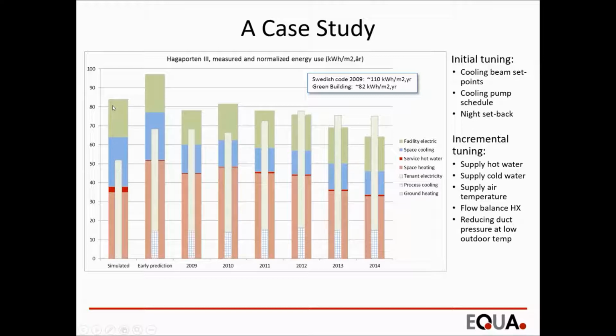The first early prediction we did based on short-term data was about 100 kilowatt hours per square meter a year. Maybe you should note also that all these years are weather normalized in the same way, so they are really comparable. Also, as you understand, we have good grip or control of how the building was used and if we had any problems and so on. So maybe I can note that in year 2010 we had some problems in the building due to a broken heat exchanger, for example.